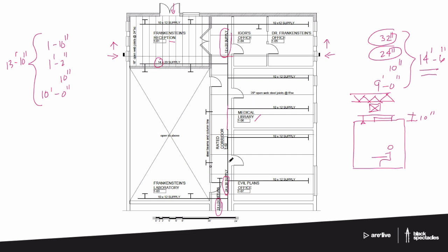What you're looking for is, what is the combination of ceiling height? Everybody's going to have the same space for lighting and sprinkler. You should check it. It might be 11 inches, it might be 8 inches, it could be a couple different numbers. 10 is the typical. But everybody's going to have that same thing anywhere in the building. But the combination of ceiling height, duct that has to be accommodated for, and then total structure, you're looking for the driving one that's going to establish the height of that second floor.